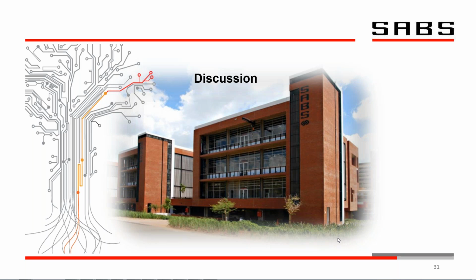Well, what we did is we did low speed balancing because they're very large rotors. If you were to full speed balance them, it would have been done at the Eskom Rotek facility at great cost. But what we did is we balanced them at low speed and we trim balanced them. You saw the one picture where we had the three technicians sitting at the side of the machine, working on the side of the machine. You can run the machines up with the covers removed and balance the rotors in situ.